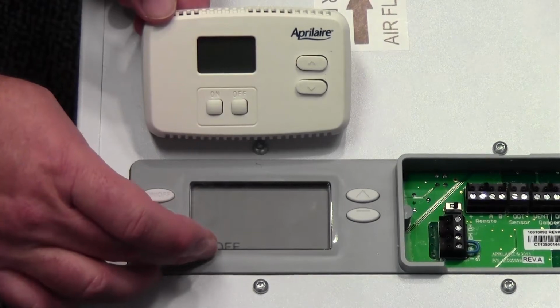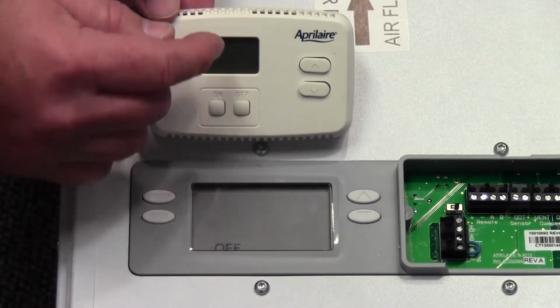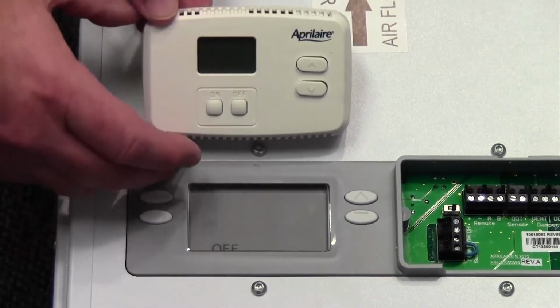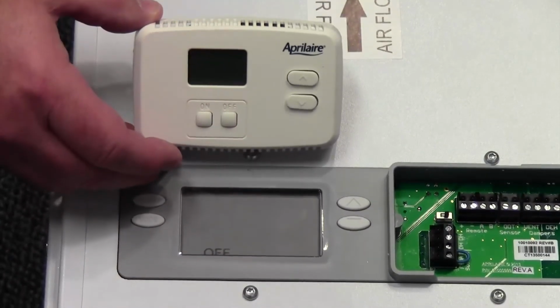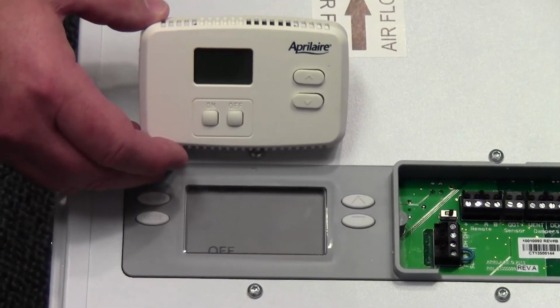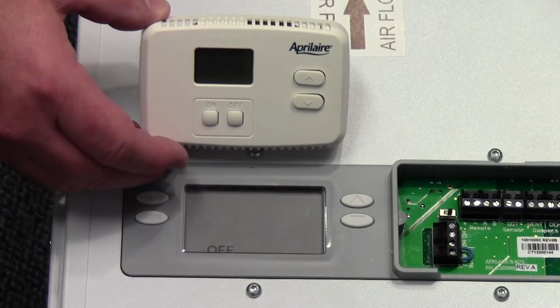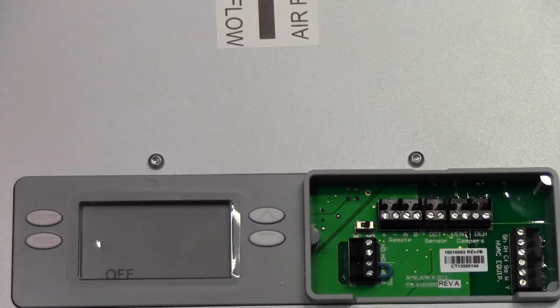If any of those diagnostic codes that I showed before appear on the screen, they would also appear on here. So very nice for those areas when we're outside of the envelope and we want to know how to run the unit and how it's working when we're inside the building envelope. Okay, so we're going to talk about the control here a little bit more. When using the onboard control, for most applications, we will just be able to walk up to the control, turn it on, and set our set point and walk away and not have to do anything else.